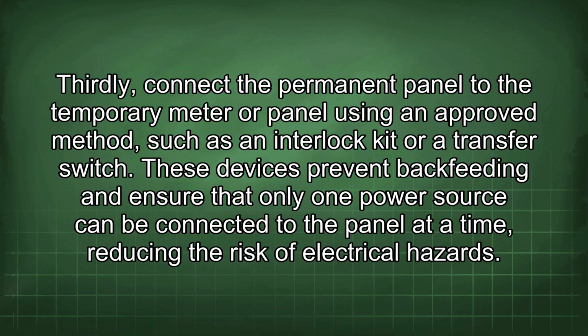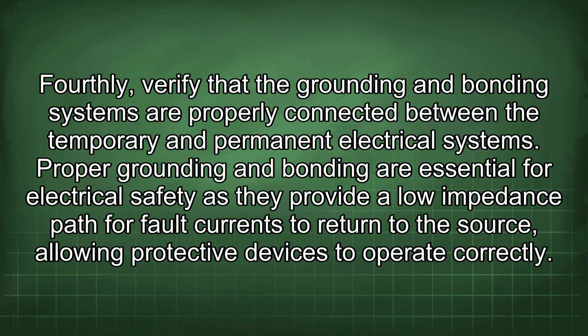Thirdly, connect the permanent panel to the temporary meter or panel using an approved method, such as an interlock kit or a transfer switch. These devices prevent backfeeding and ensure that only one power source can be connected to the panel at a time, reducing the risk of electrical hazards. Fourthly, verify that the grounding and bonding systems are properly connected between the temporary and permanent electrical systems. Proper grounding and bonding are essential for electrical safety as they provide a low impedance path for fault currents to return to the source, allowing protective devices to operate correctly.